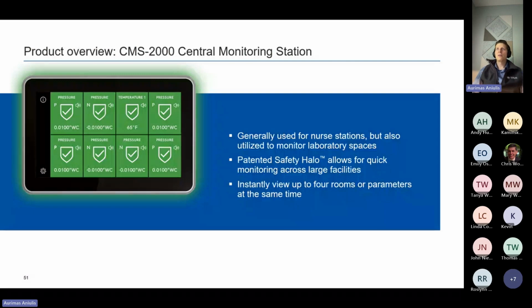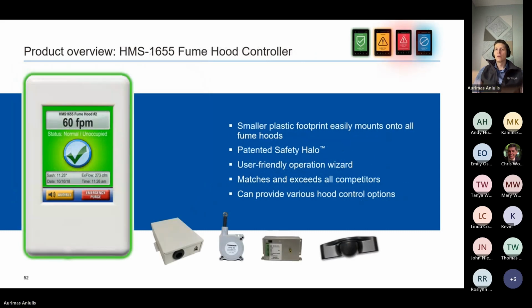Secondly, our CMS 2000 central monitoring station, great for a nurses' station. If they've got 8 different rooms and they're trying to monitor the pressure, occupancy, or whatnot, it's one little display. If there's an alarm condition down another ward or a couple of doors away, they don't have to run and look. They can look at this and see exactly which room it is and make their decision accordingly. That CMS, by the way, is also in the specs. They say you've got to have a nurse's station.